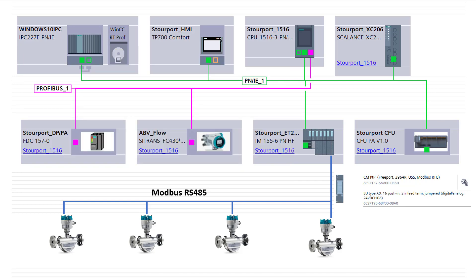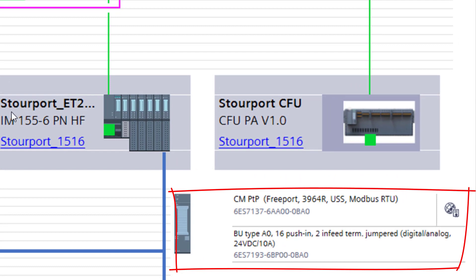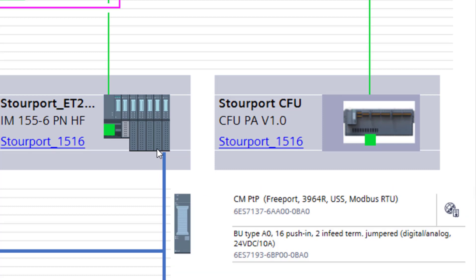What we can do is we can add a Modbus Master Card to your ET200SP IO here, or you could add it to a 1200—there's a 1200 Modbus card—and then multi-drop into that instrument. And there's faceplates that you can download to connect to the instruments via HMI, which is quite nice. And that all works fine.